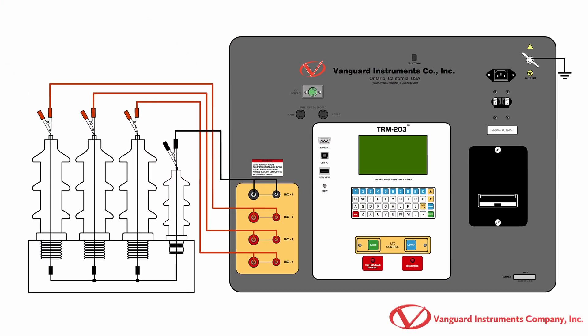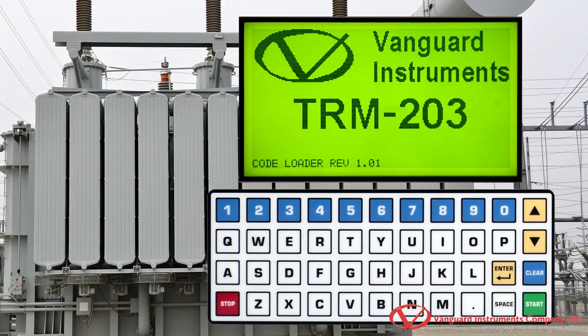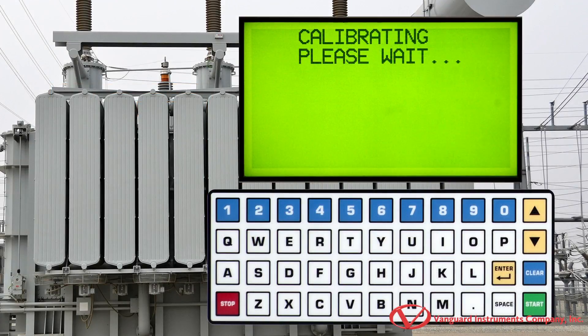Before we can start performing a winding resistance test, we'll need to make the proper connections to the device under test, per this illustration. Once the proper connections have been made, we'll start from the TRM203's main menu.